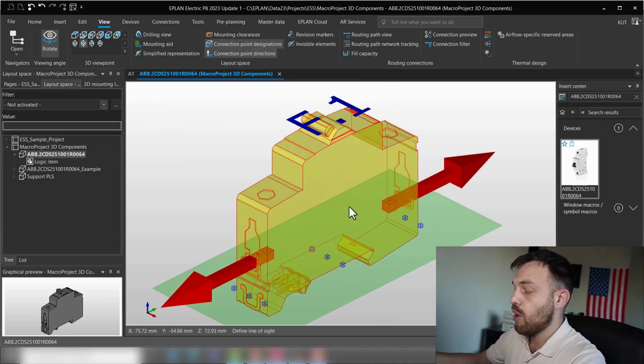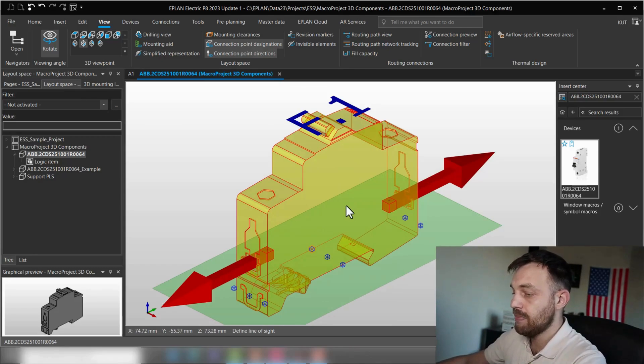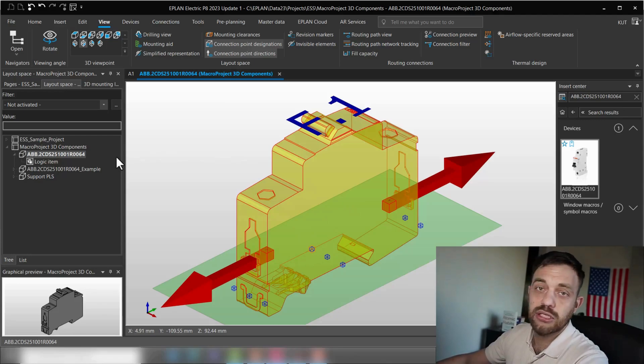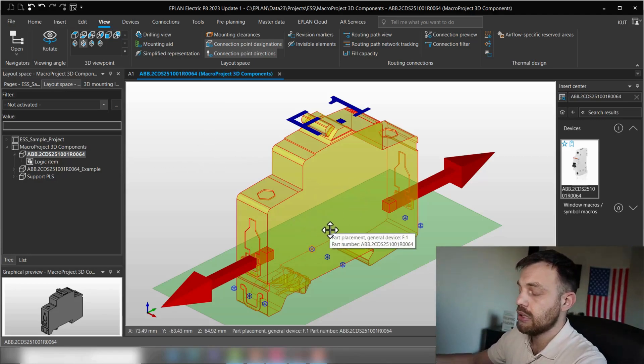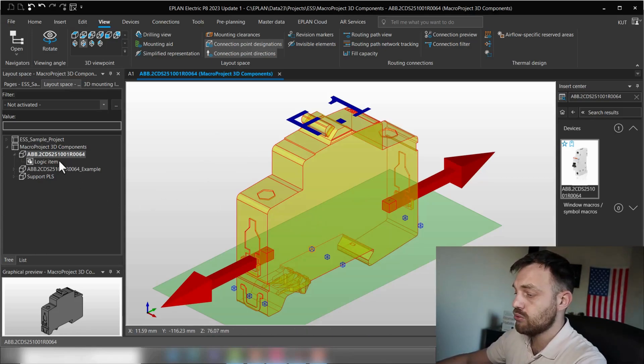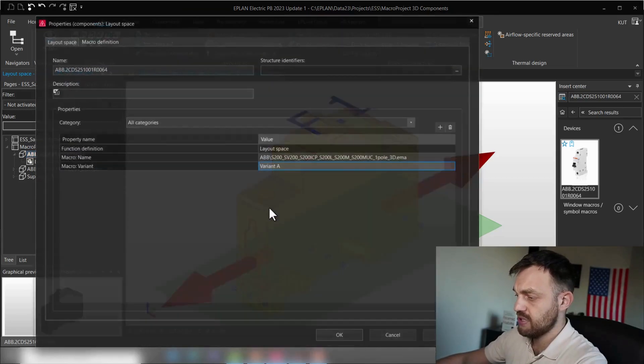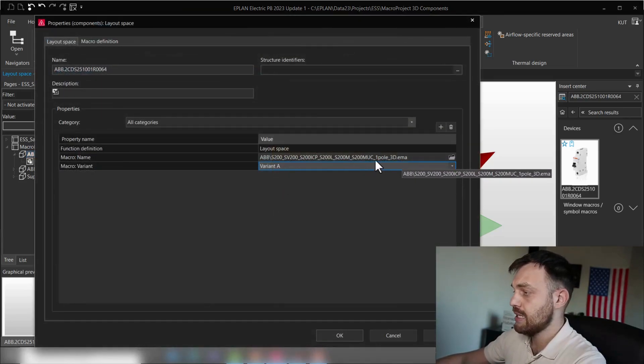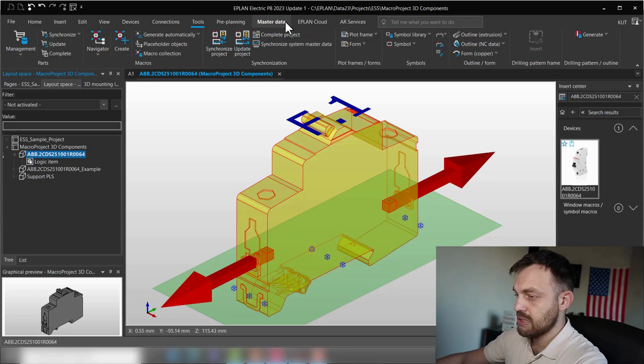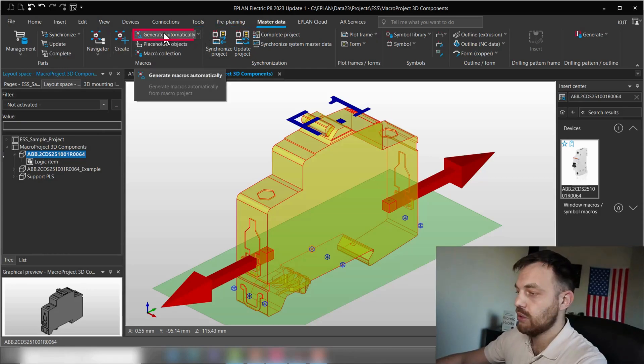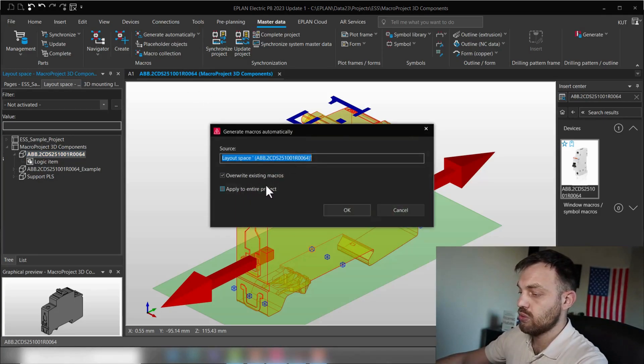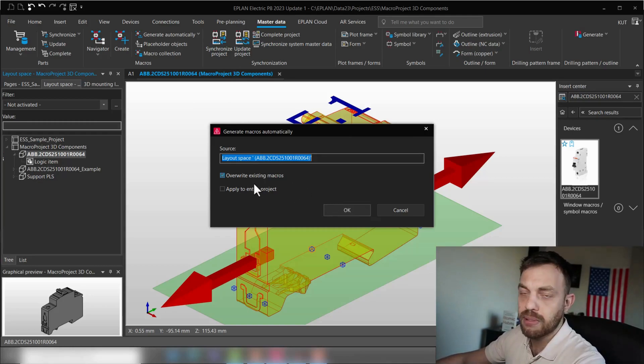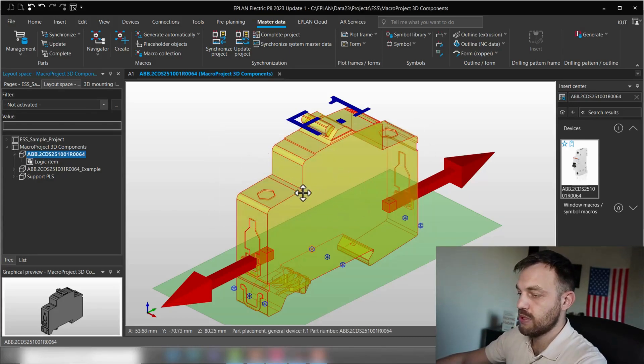And yeah, this will be how I would recommend you to create connection point patterns. Now, if we are happy with the macro, we will need to generate it and then place the component in our enclosure. So how to generate the macro? So as I said before, it's very important to have this macro assigned. And now you can just select it and under master data and the macros generate automatically. The software will ask you if you would like to overwrite existing macros, which we definitely want. We don't want to apply to the entire project. Just press OK. The macro was created.